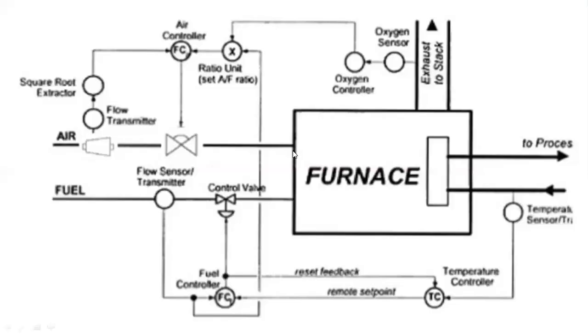This is another method of controlling the furnace using a ratio controller. You are sensing the oxygen in situ with online measurement and giving the signal to a controller that opens or closes the fuel line valve and controls the air blower. A flow transmitter senses the flow, and proportionately determines how much air should be given. The ratio controller gives a signal to the flow controller, which decides the proportional air amount. A similar approach applies to the fuel, where the control valve is adjusted based on the available temperature feedback.